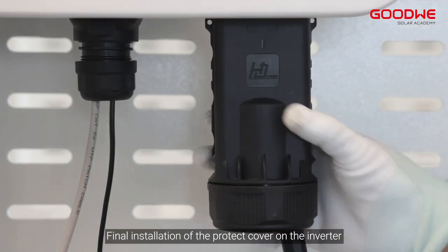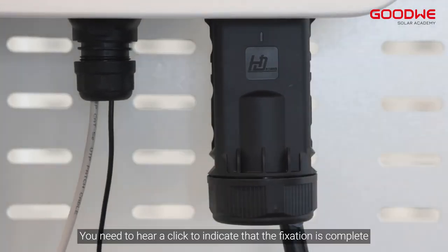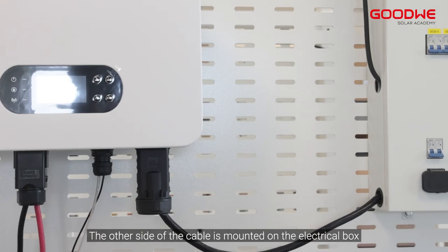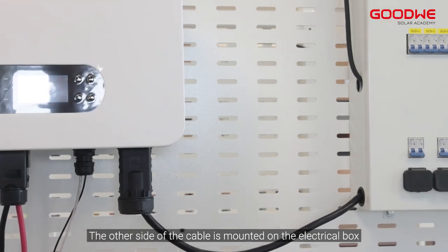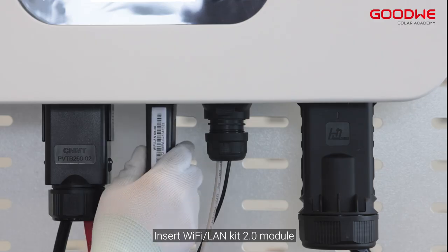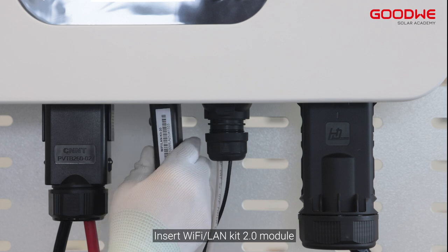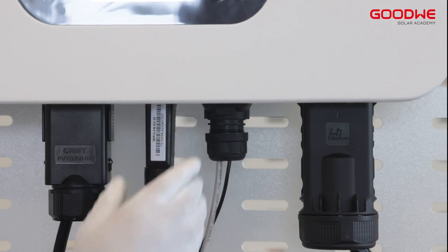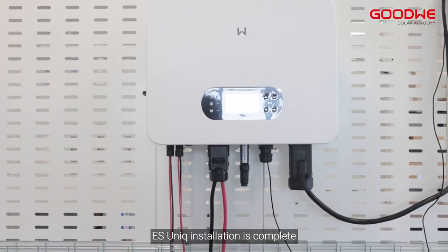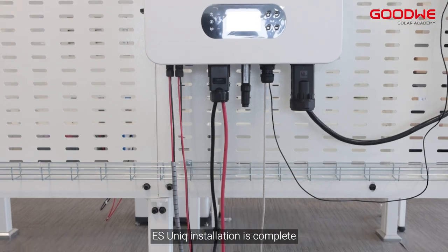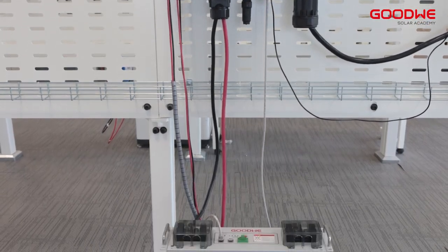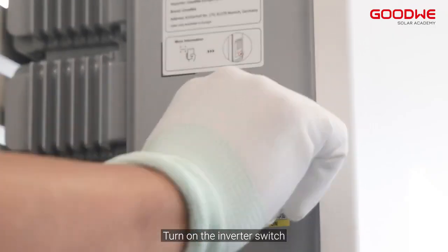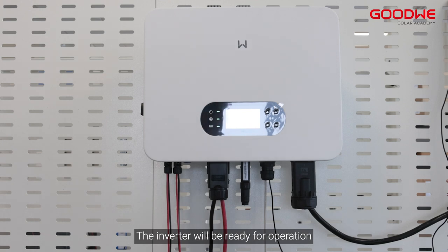Final installation of the protect cover on the inverter. You need to hear a click to indicate that the fixation is complete. The other side of the cable is mounted on the electrical box. Insert Wi-Fi/LAN kit 2.0 module. ES Uniq installation is complete. Turn on the inverter switch. The inverter will be ready for operation.